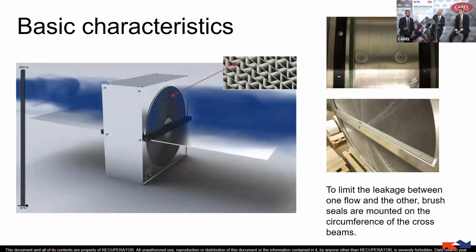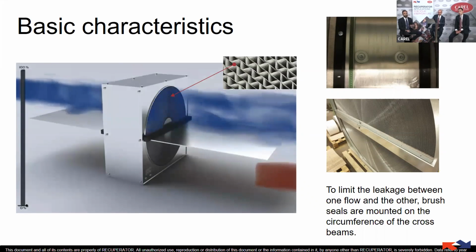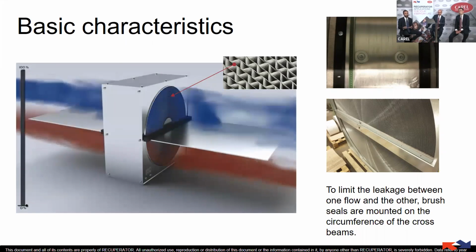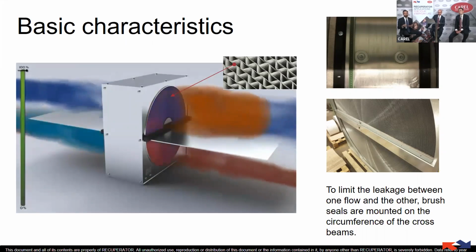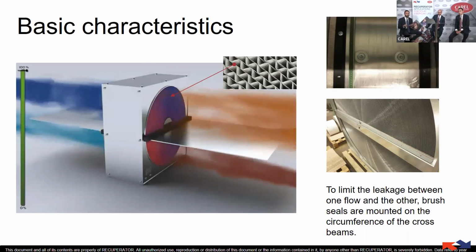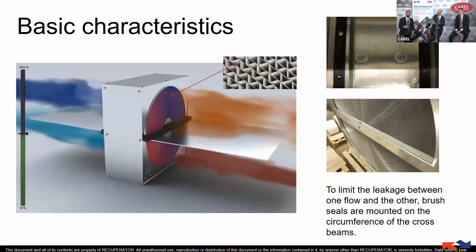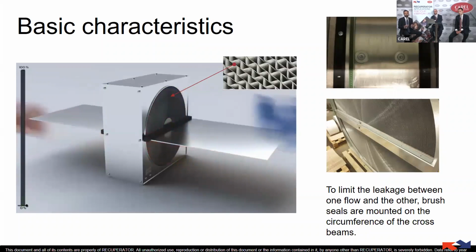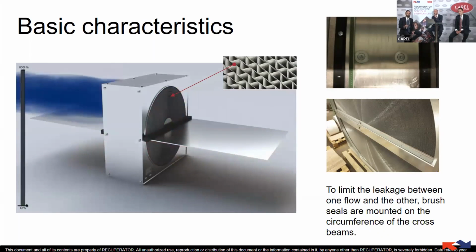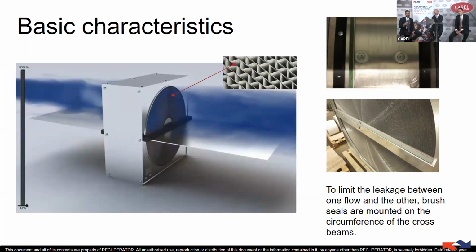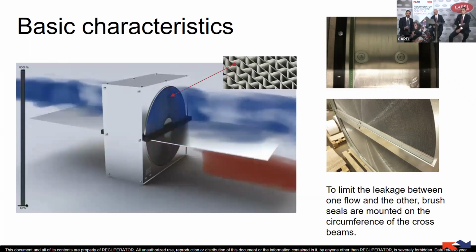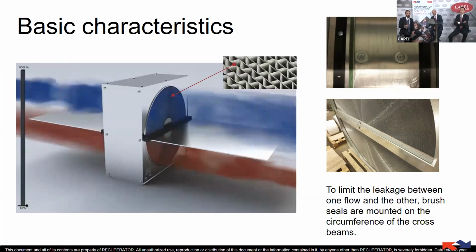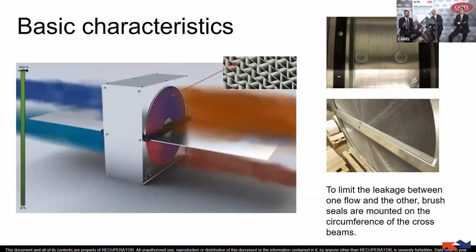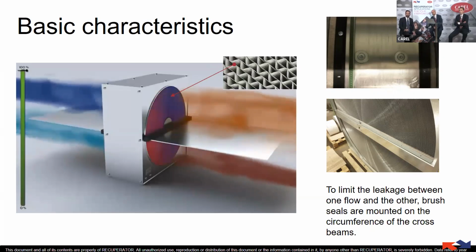The rotary heat exchanger has the same main target as the plate heat exchanger, but in this case we don't have a static component. It is composed of a moving rotor made of a honeycomb matrix material that rotates between two airflows that are different in temperature and humidity. It is able to absorb the heat from one airflow and release it during the rotation to the opposite airflow. Of course, the rotor is moved by a motor and is inside a casing. The honeycomb structure is really permeable to the air, to increase the efficiency as much as possible and to keep the pressure drop down.